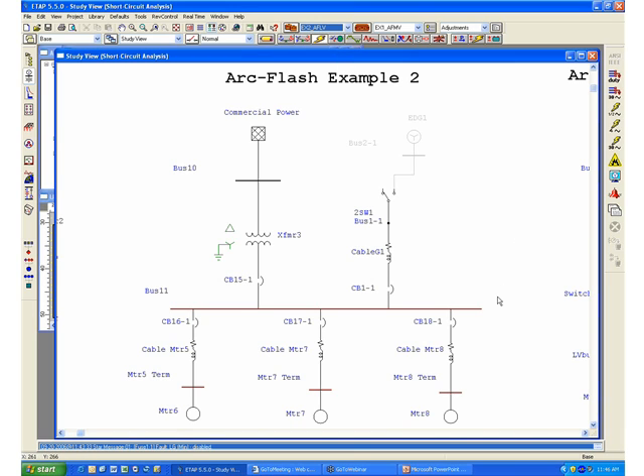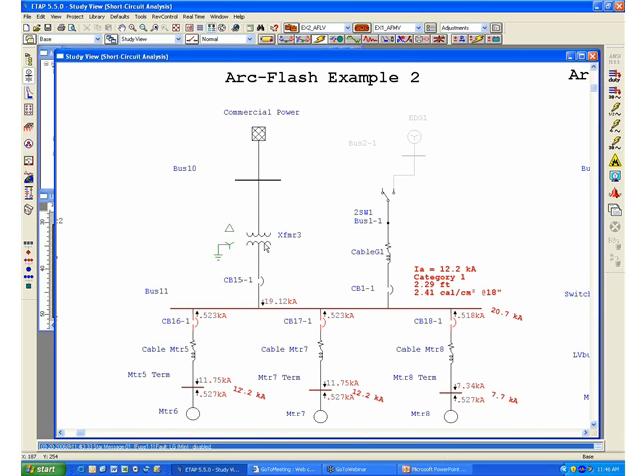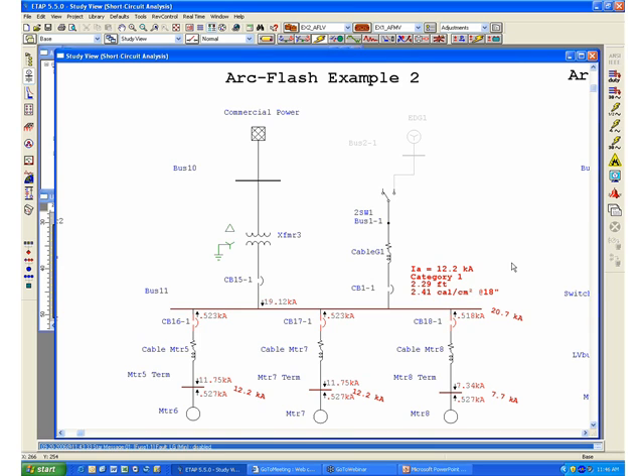Under normal operation, the program has determined that you have a category one with 2.41 calories per centimeter squared. Of course, we have to determine other operating conditions, which would be the case where you're operating the system from the emergency diesel generator on its own.